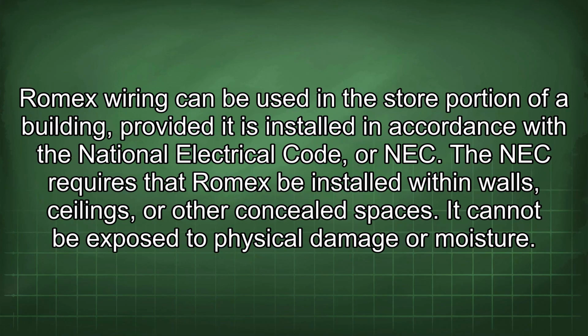Romex wiring can be used in the store portion of a building provided it is installed in accordance with the National Electrical Code, or NEC. The NEC requires that Romex be installed within walls, ceilings, or other concealed spaces. It cannot be exposed to physical damage or moisture.